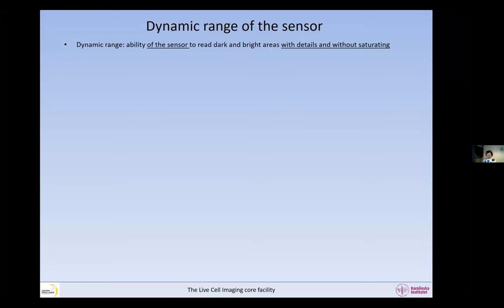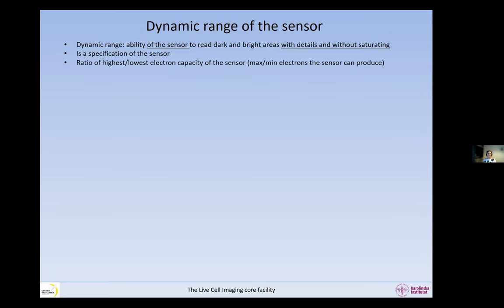The dynamic range is a ratio of electrons — the highest number divided by the lowest number of electrons the sensor can produce. The lowest limit is the readout noise. When we amplify and convert the signal, we create readout noise — that is the minimum signal. If we have no light at all, we will anyway have a few electrons that will be read. The highest limit is called the full well capacity, measured in electrons — the maximum number of electrons before the sensor saturates.